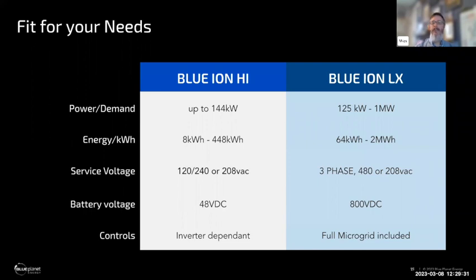With the HI, we do either 120/240 volt, your regular residential service, or 208 three-phase, which is commercial service. The battery voltage is 48 volts, and the controls, what you can do with the battery, depends on which inverter you choose. Most installers have inverter brands they're comfortable with, and that inverter ecosystem determines what the Blue Ion HI can do.